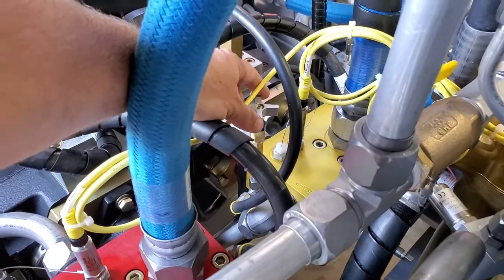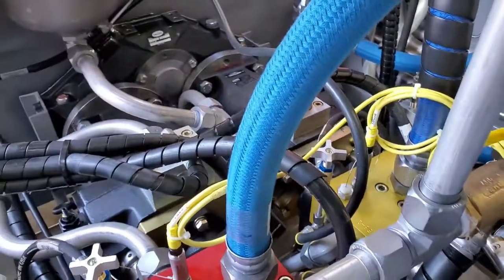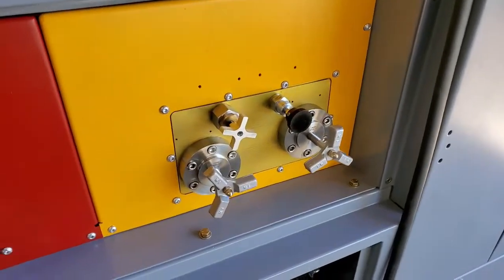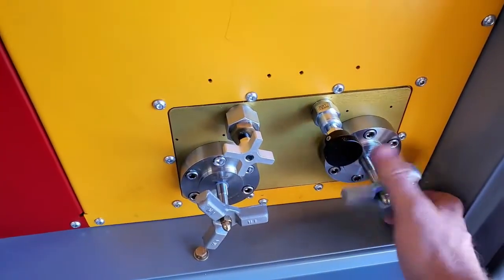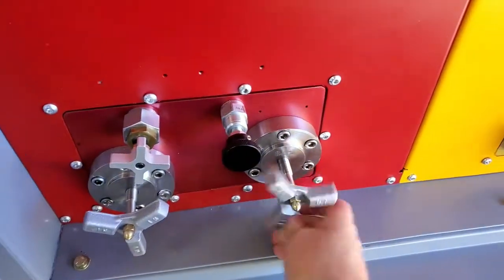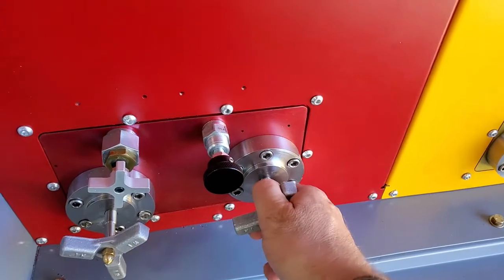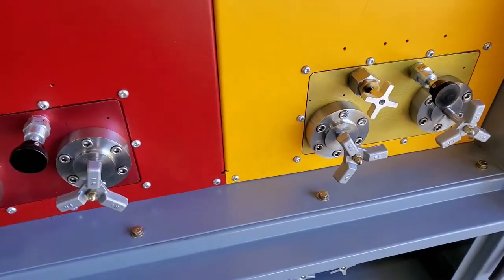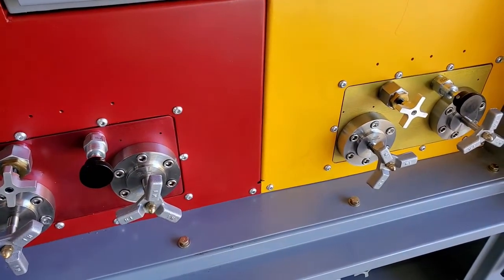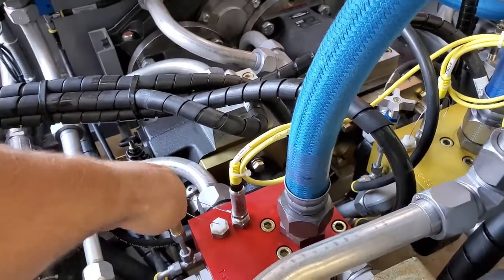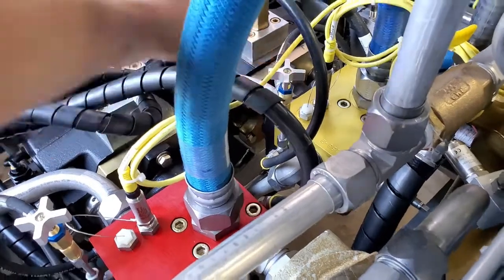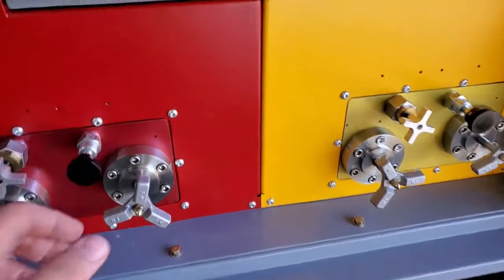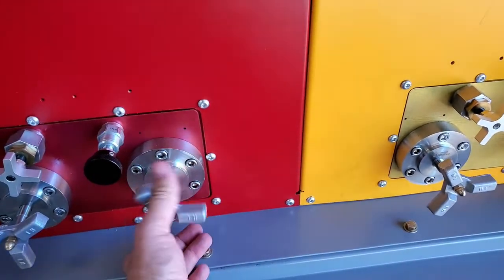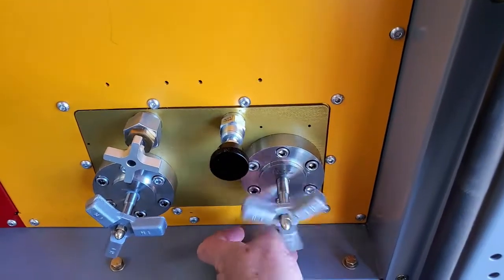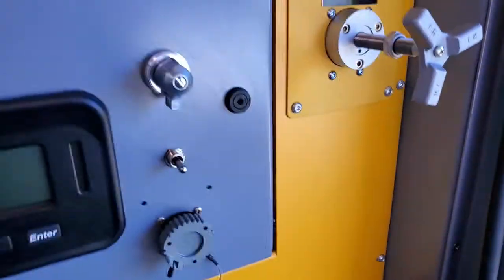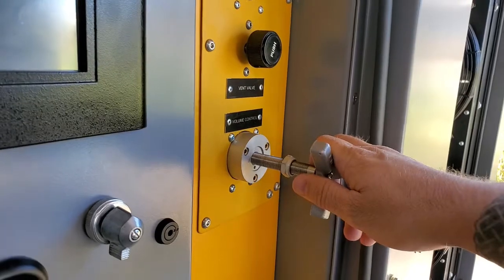What this does is it allows boost pressure to enter into the volume control system. Now, back on the front of the unit, with those two valves still open, you're going to go ahead and close your bypass valves. And this is going to give you anywhere from 60 to 90 psi on your boost system. Once those are closed and you have 60 to 90 psi, go ahead and close the two valves on the boost pumps. Clockwise and clockwise to close. Reopen your bypass valves. And now you should have full control of your volume control from maximum all the way down to a minimum of around 5 gallons per minute.